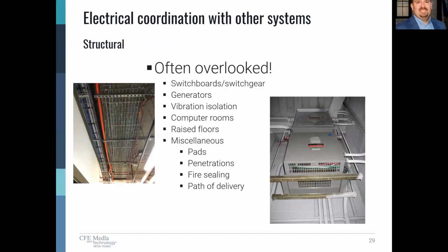One element of coordination with electrical that's often overlooked is coordination with structural. If you think about the items that we're putting into a building, the switchgear, the switchboards, the generators, these things have excessive amounts of weight associated with them, comparable to automobiles or a small truck, for example. The structural integrity of the building needs to be able to support these elements in the space.